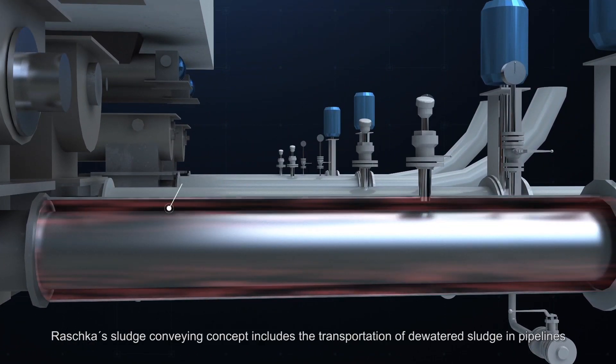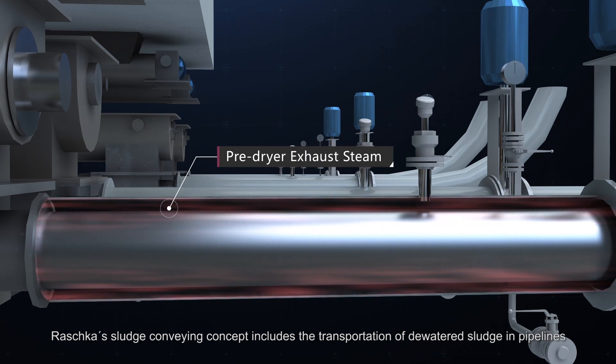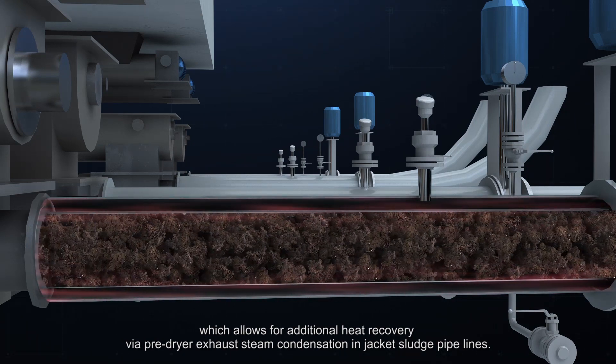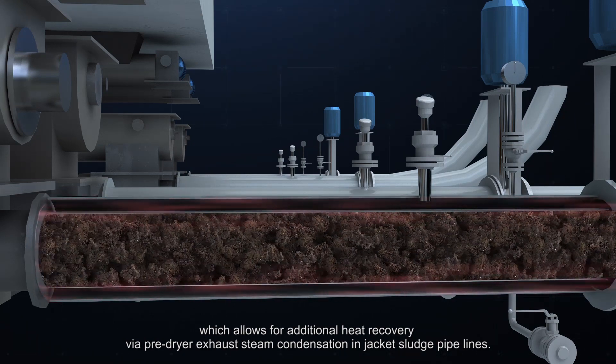Raschka's sludge conveying concept includes the transportation of de-watered sludge in pipelines, which allows for additional heat recovery via pre-dryer exhaust steam condensation in jacket sludge pipelines.